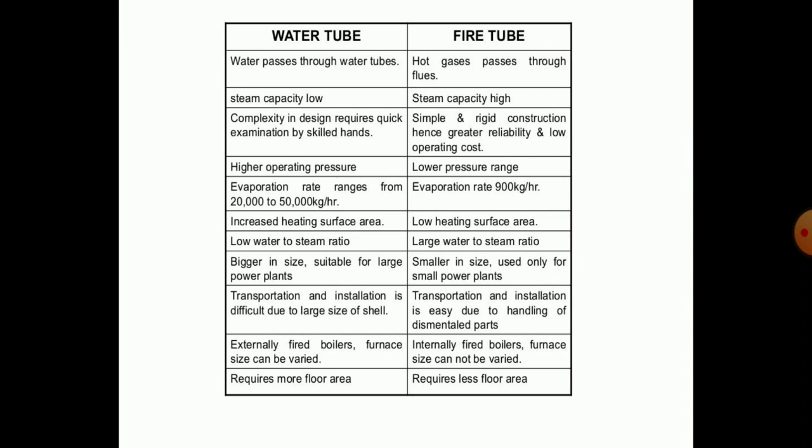Compared to water tube boilers, in fire tube boilers, hot gases pass through the tubes, and they have simple and rigid construction, giving greater reliability and low generation cost. Pressure ranges are low and evaporation ranges up to 900 kg per hour. They have a low heating surface area and a large water-to-steam ratio, and are smaller in size, used only for small power plants. These are the points which differentiate fire tube and water tube boilers.